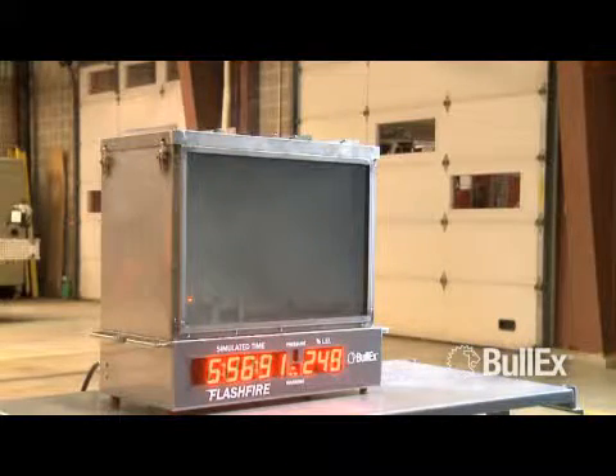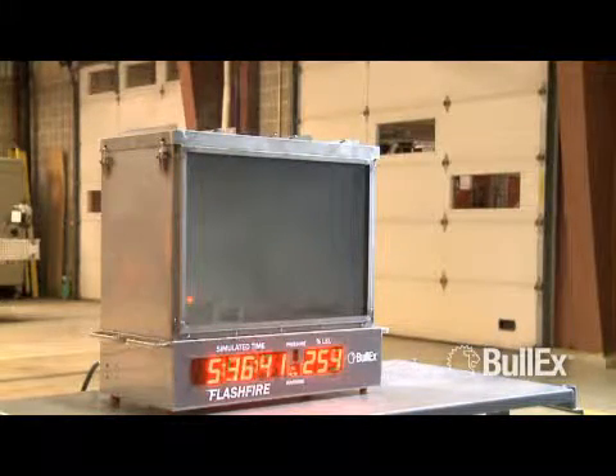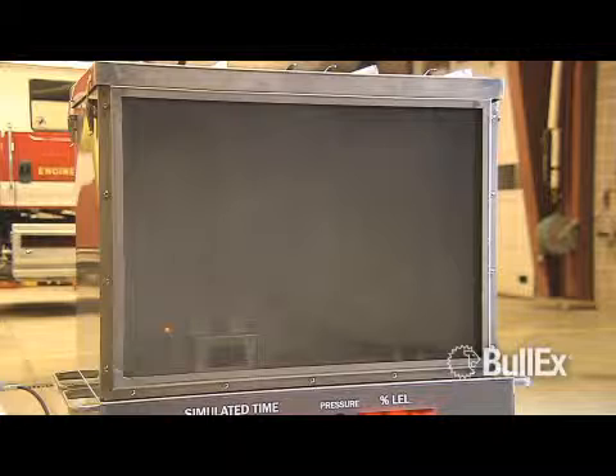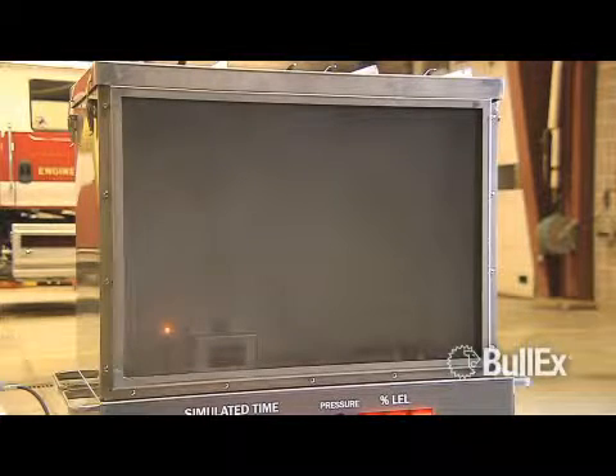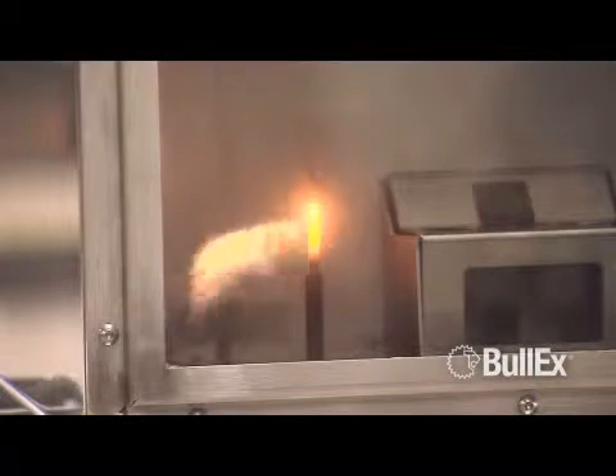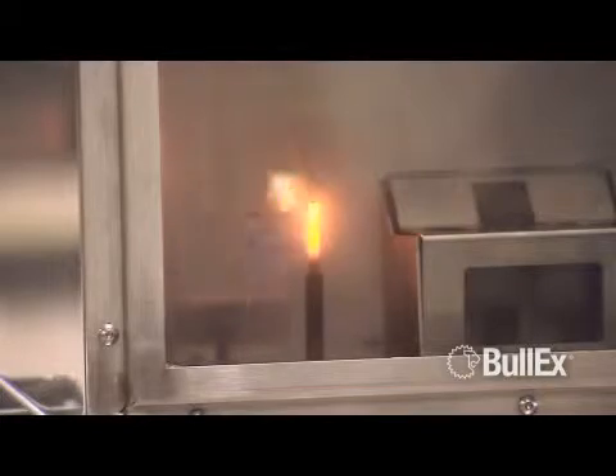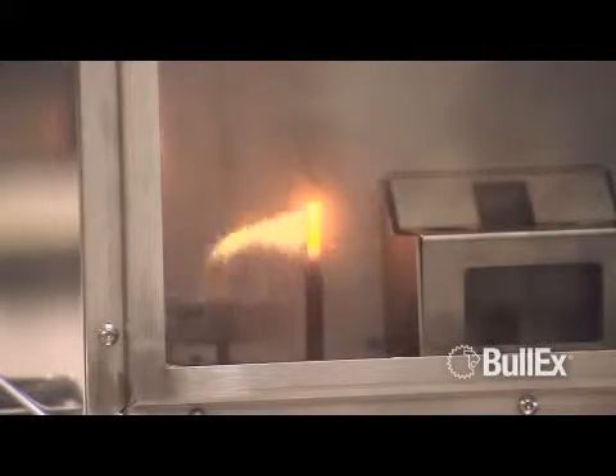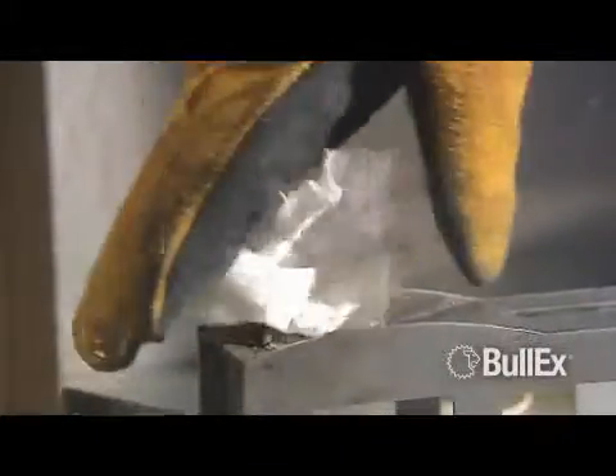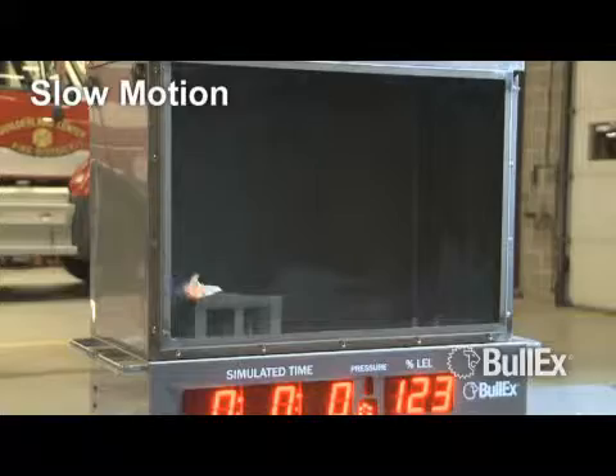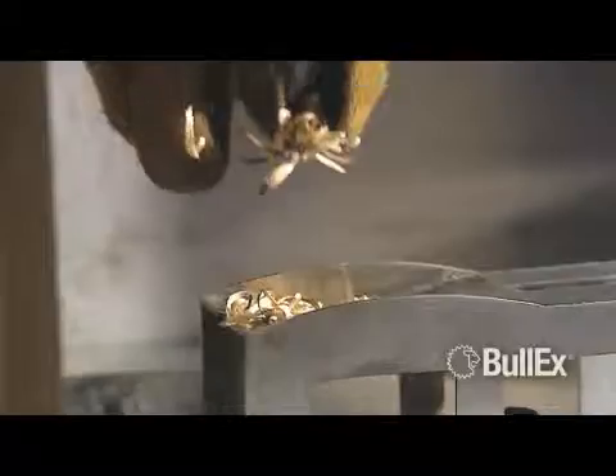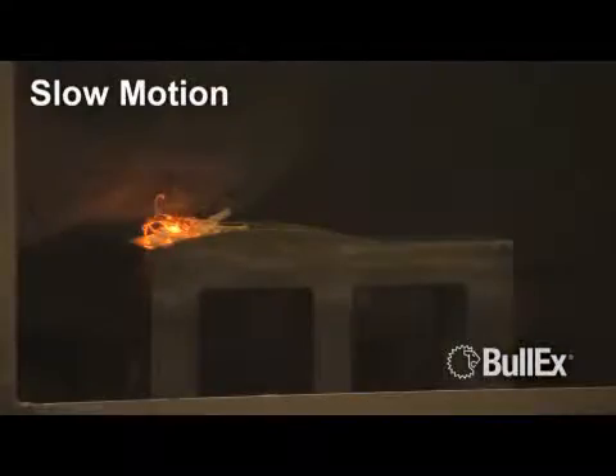Flashovers demonstrate the sudden, rapid deterioration of conditions that occur when combustible materials inside a room reach their auto-ignition temperature. A hot point source is used to simulate the seat of fire, and when the conditions are right, the room suddenly flashes. The FlashFire system can also demonstrate auto-ignition of solids to show how off-gassing causes combustibles in rooms to rapidly ignite in flashover conditions.